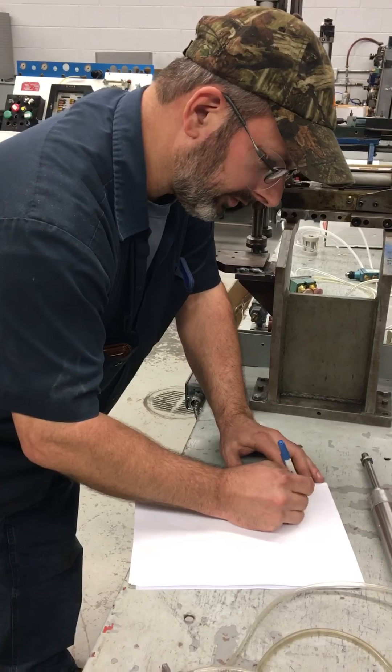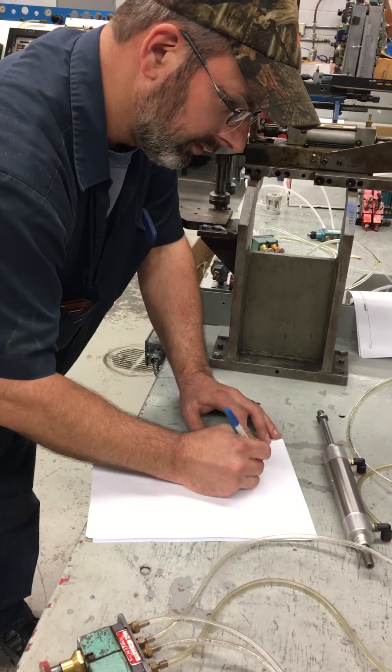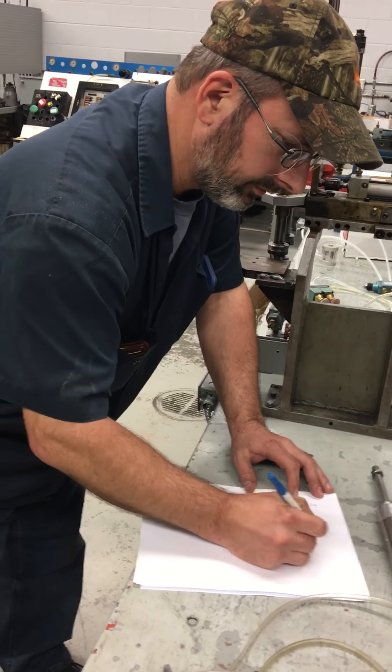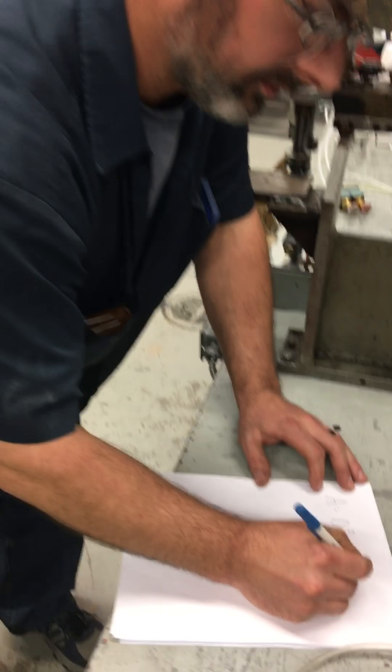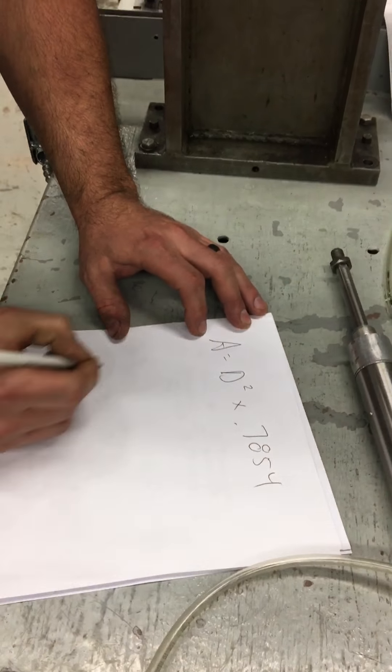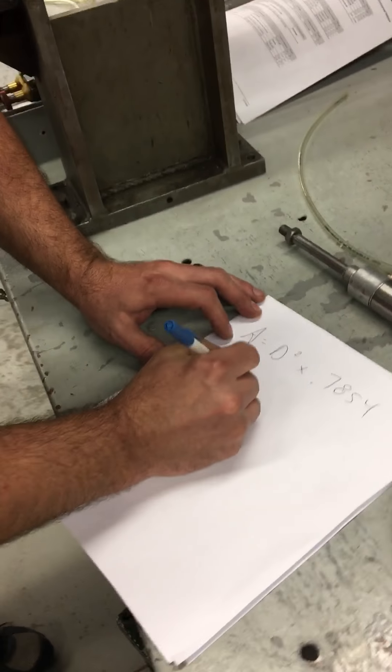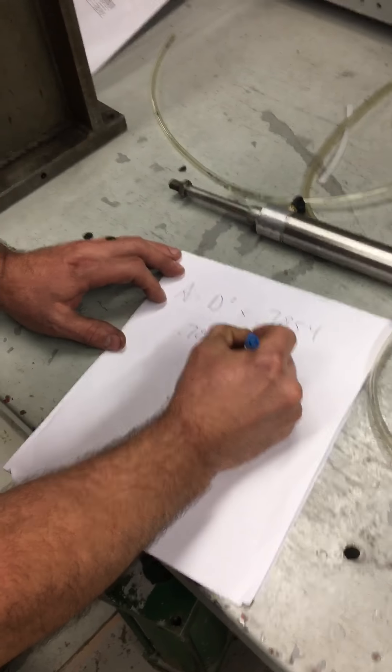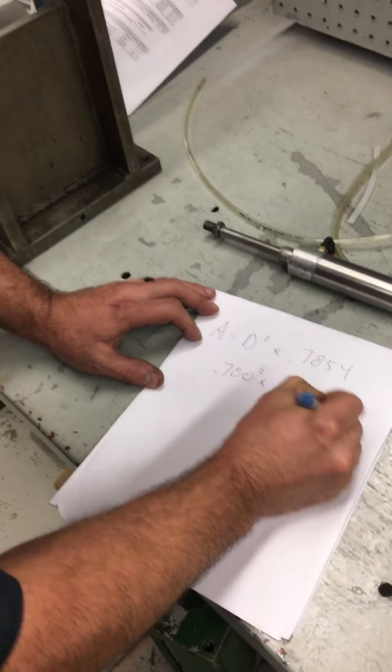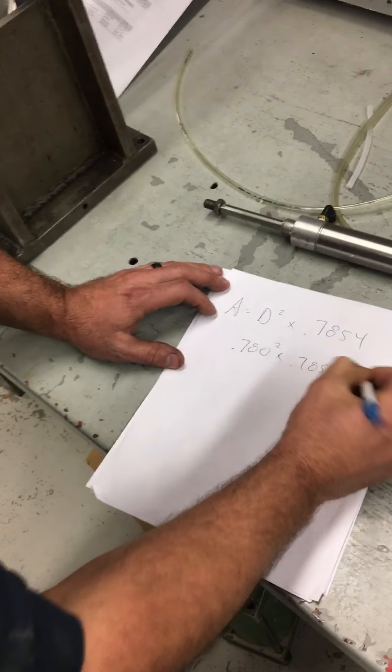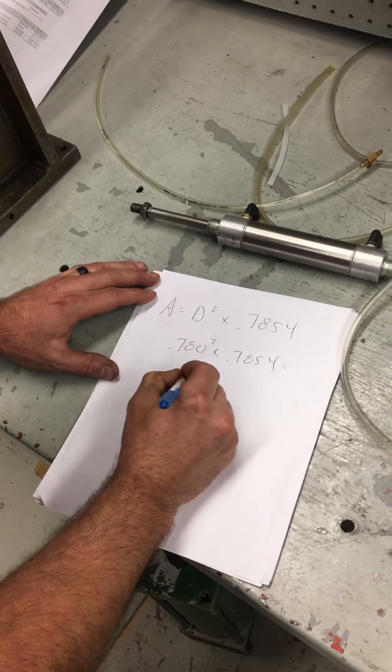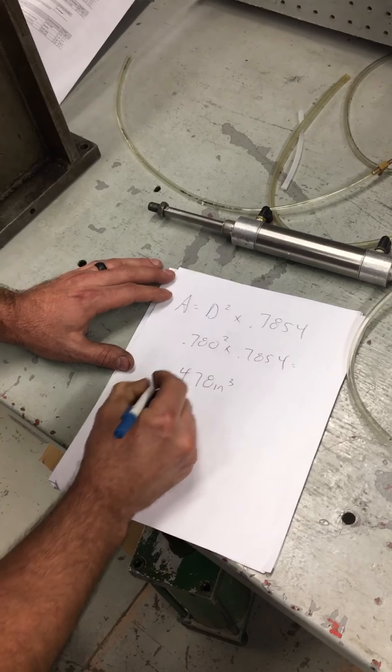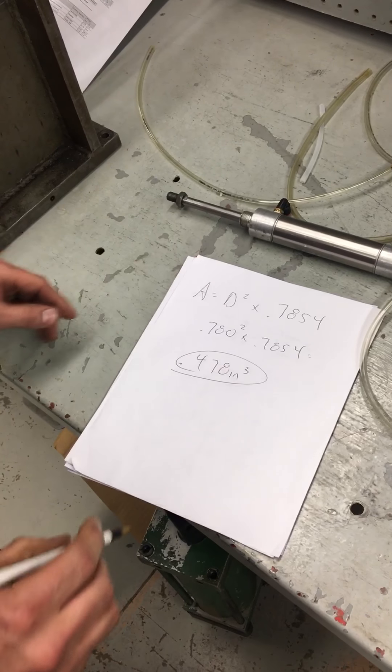So we know what area is equal to: diameter squared multiplied by 0.7854. So we know what our diameter is. That is 0.780 squared. So we came up with an answer of 0.478 square inches. Okay, that takes care of our area for our piston.